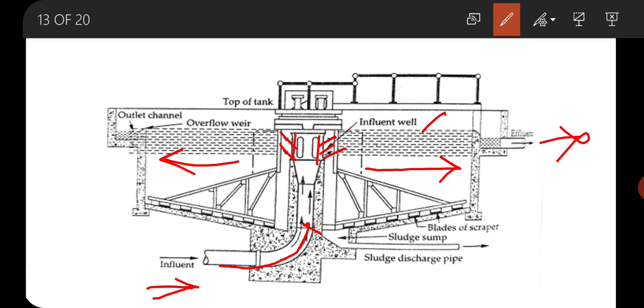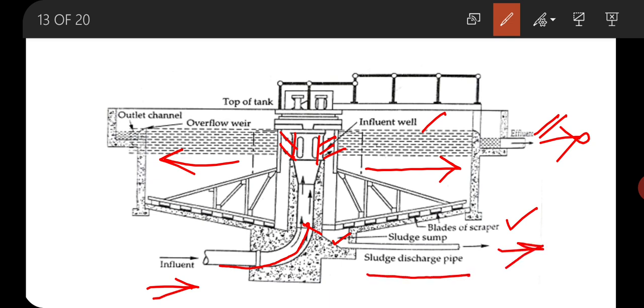This is the effluent side, through which the clear water is taken out. Here are the blades of scrapers and this is the sludge sump. The sludge is scraped to the central sump, and the mechanical scraper continuously removes the sludge from where it is withdrawn during operation. This is the sludge discharge pipe through which the sludge is taken out.